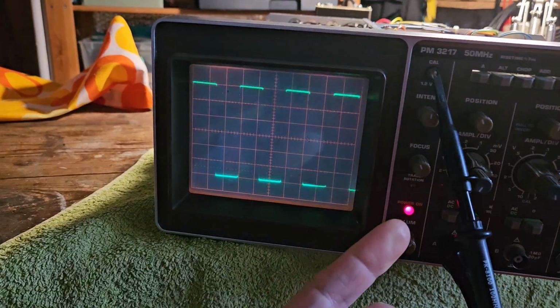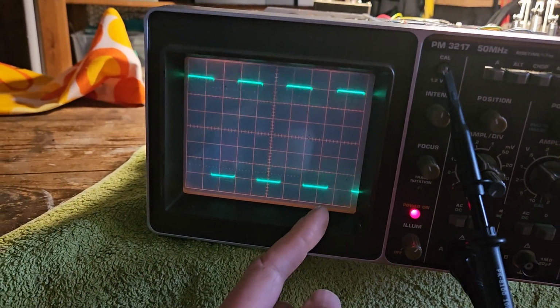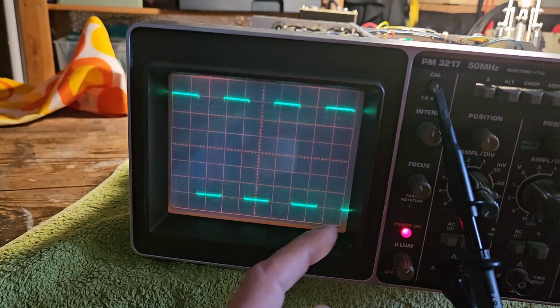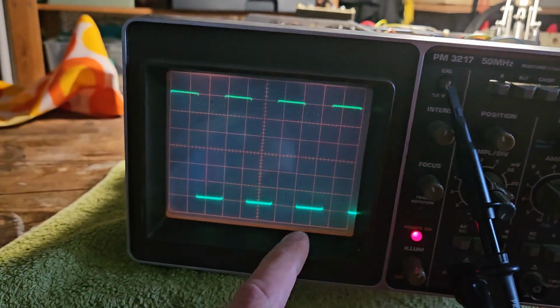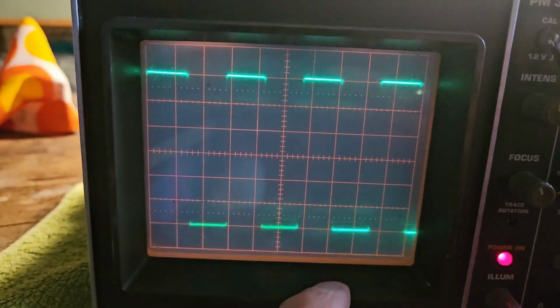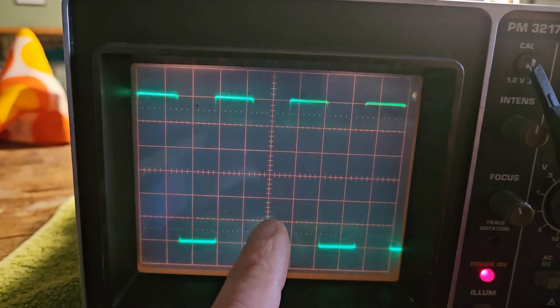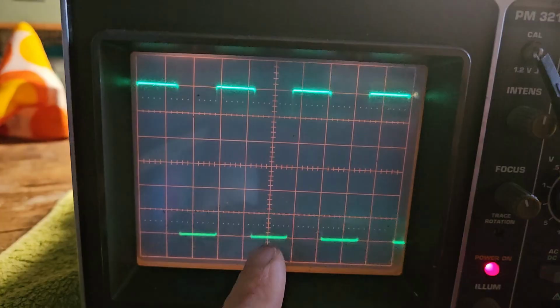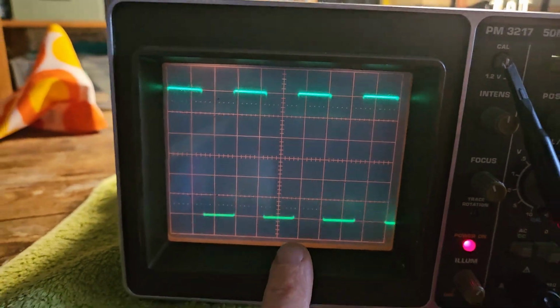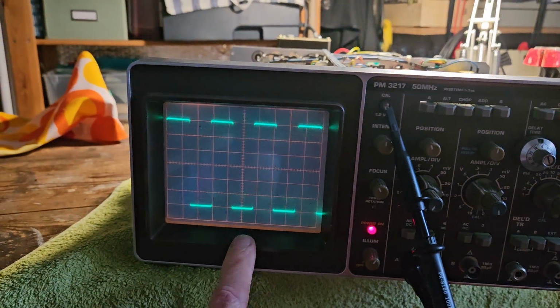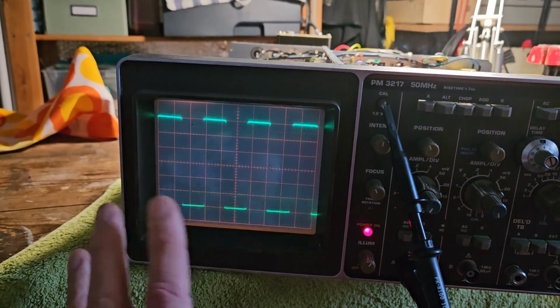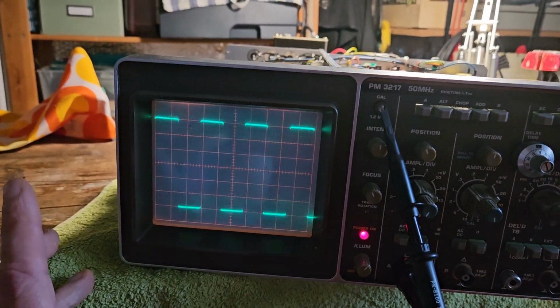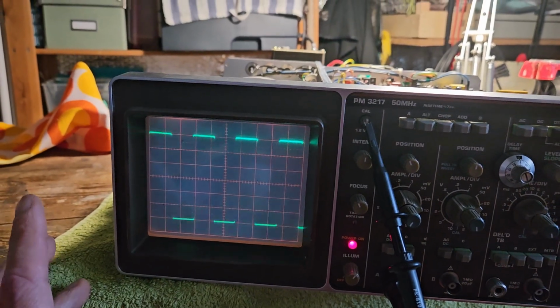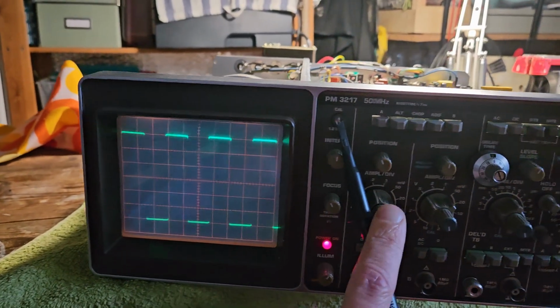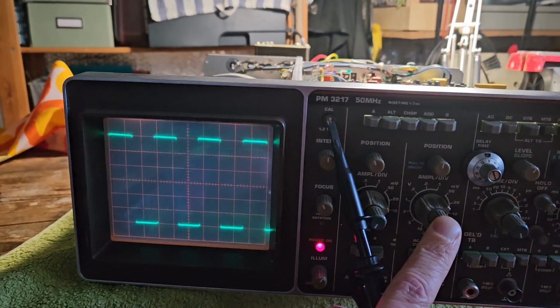Now looking at the calibration of the internal amplifier based on this now calibrated voltage, we can see similarly 6 divisions there on the vertical scale, so that's looking like as good as we're going to get on this kind of scope. So yep, no need to adjust anything on the vertical amplifier. Of course that's only one channel, that's the A channel, so we'll have to check the second one as well.